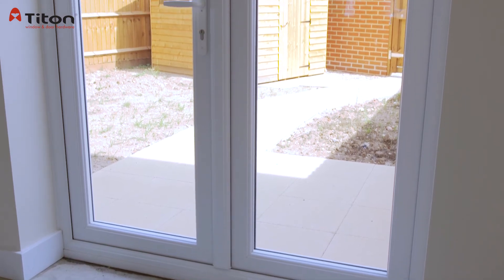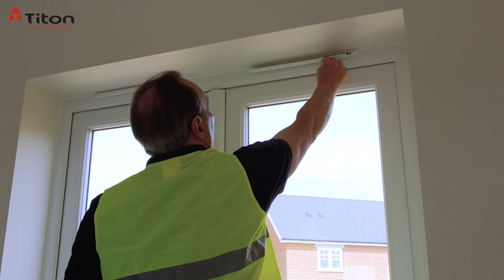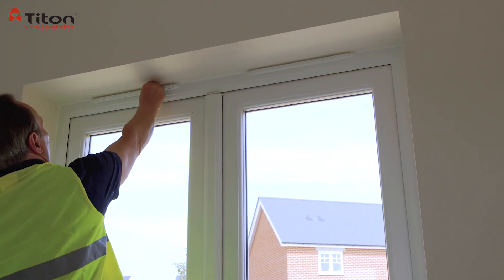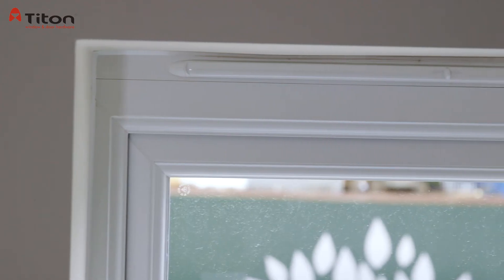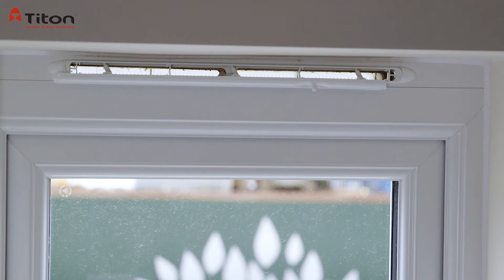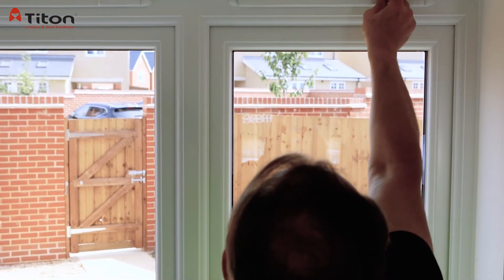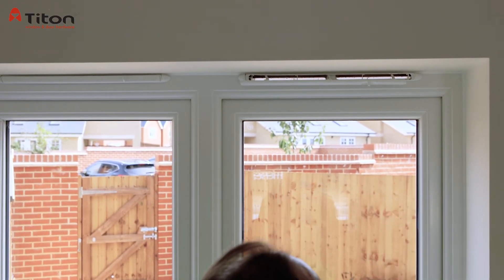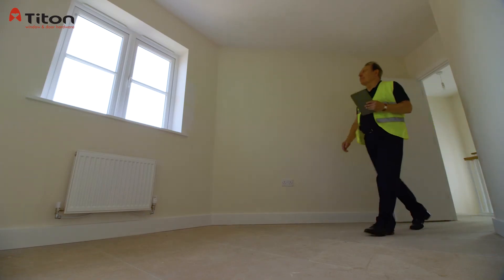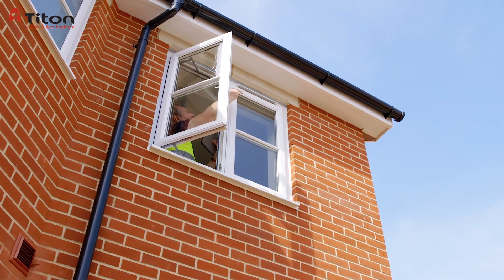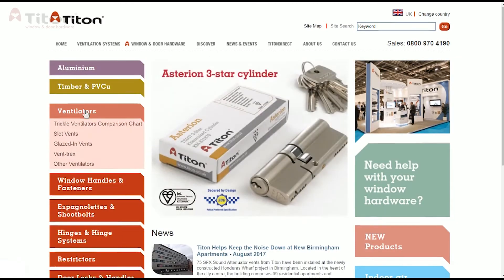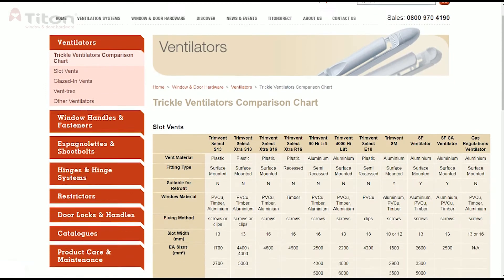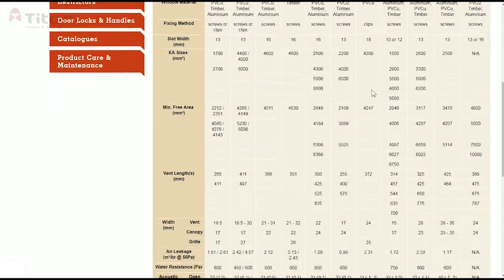In each room, as well as adding up the vents, the person checking should ensure the vents are approximately 1.7 metres above floor level to keep undue draughts to a minimum. Each vent should be marked with an EA figure — some have a label, others are moulded in. It pays to check whether the slot behind the vent looks to be the right size for the vent; it shouldn't be much smaller than the vent length or width, otherwise the tested amount of air won't flow through, and should be evenly cut. The operation of the vent should also be checked in case someone has painted or plastered over them since the windows were fitted. There should be a cursory check of the external part of the vent — usually the bit with the grill in it — to see that it is fitted correctly on the outside of the property and not blocked. The details of all the vent, slot, and canopy combinations, which is how the vent manufacturers come up with their tested figures, should be available on the vent manufacturer's website, or if not clear, from the window manufacturer who fitted them.